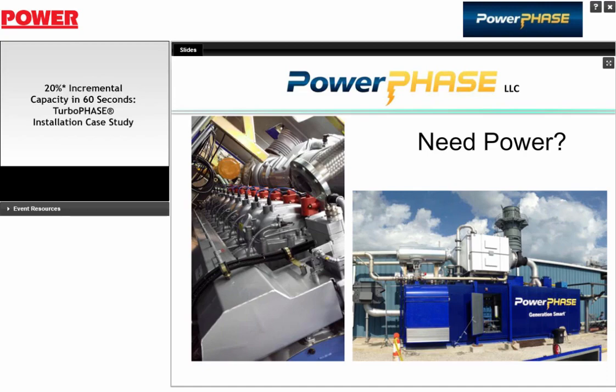All right. Another question about your fuel choice. Why not use natural gas engine drive instead of diesel? Okay, so the picture of the presentation that we just did at the Morris plant is natural gas. It's a 2 megawatt natural gas machine, and that same 2 megawatt box works on every gas turbine and makes, at this power plant, a little over 3 megawatts on the gas turbine, and on a 7FA makes over 5 megawatts on the gas turbine. So this module is natural gas.